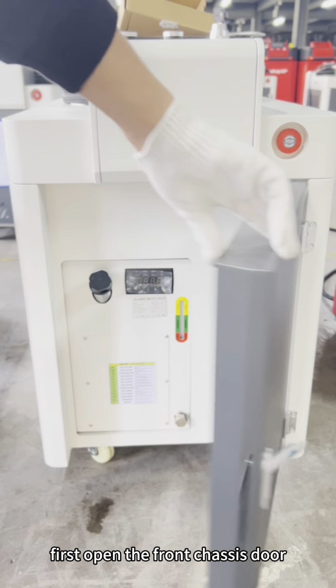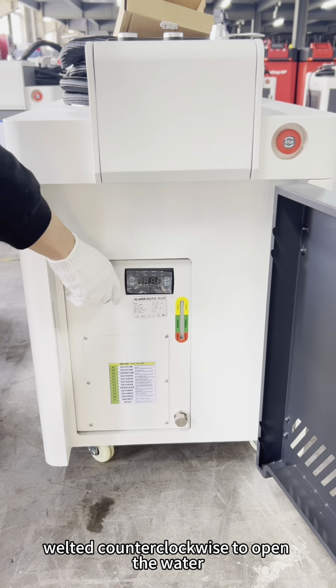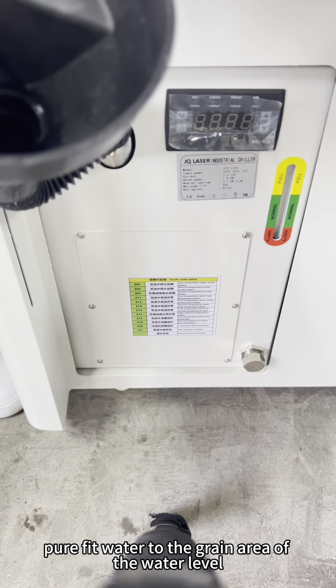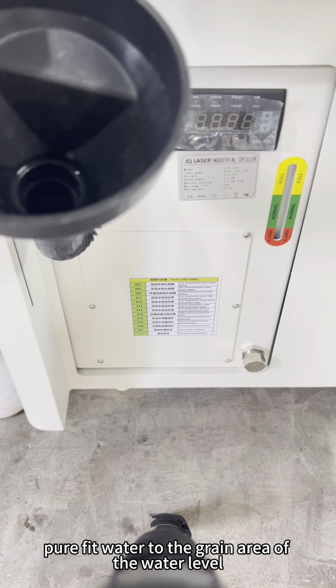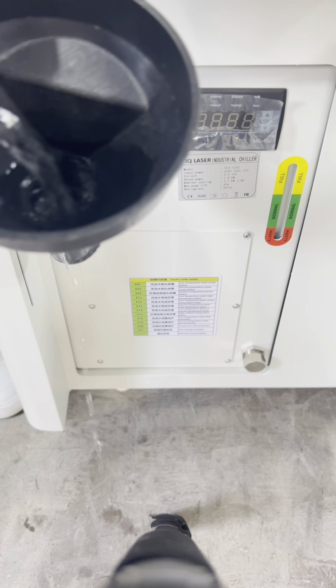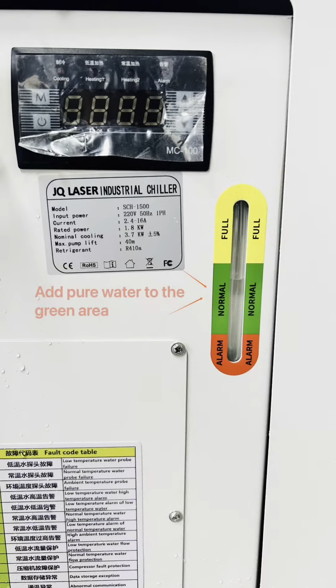1. Adding water to the chiller. First, open the front chassis door. Rotate counterclockwise to open the water inlet of the chiller and add purified water to the green area of the water level marking line on the chassis. 2. Turn on the power supply.